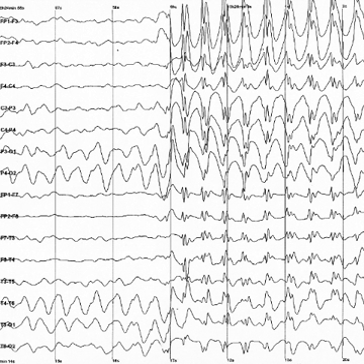Analog-to-digital sampling typically occurs at 256 to 512 Hz in clinical scalp EEG. Sampling rates of up to 20 kHz are used in some research applications. During the recording, a series of activation procedures may be used. These procedures may induce normal or abnormal EEG activity that might not otherwise be seen. These procedures include hyperventilation, photic stimulation with a strobe light, eye closure, mental activity, sleep and sleep deprivation.